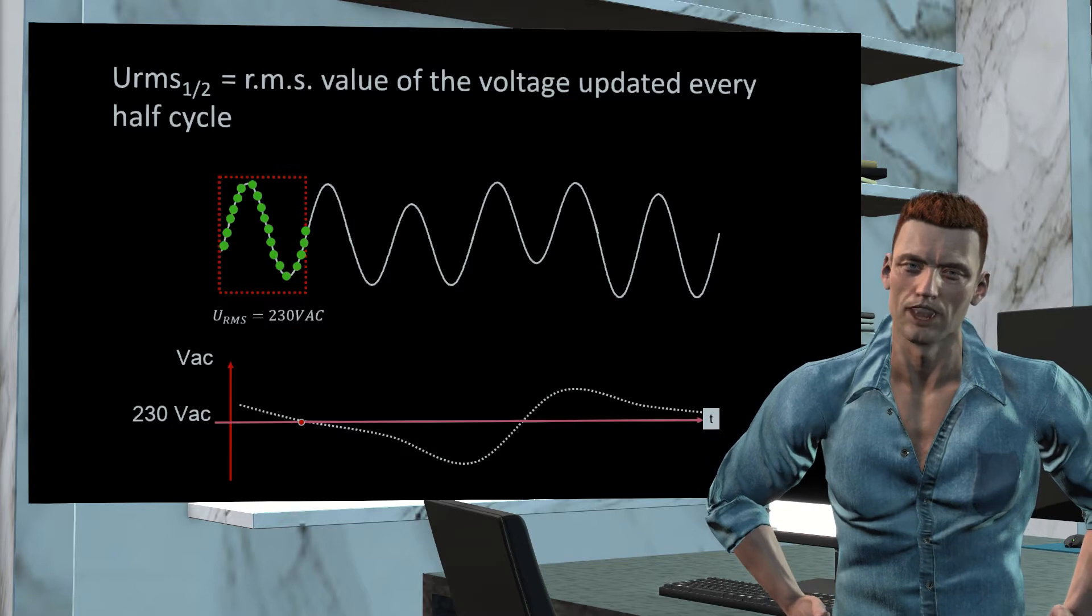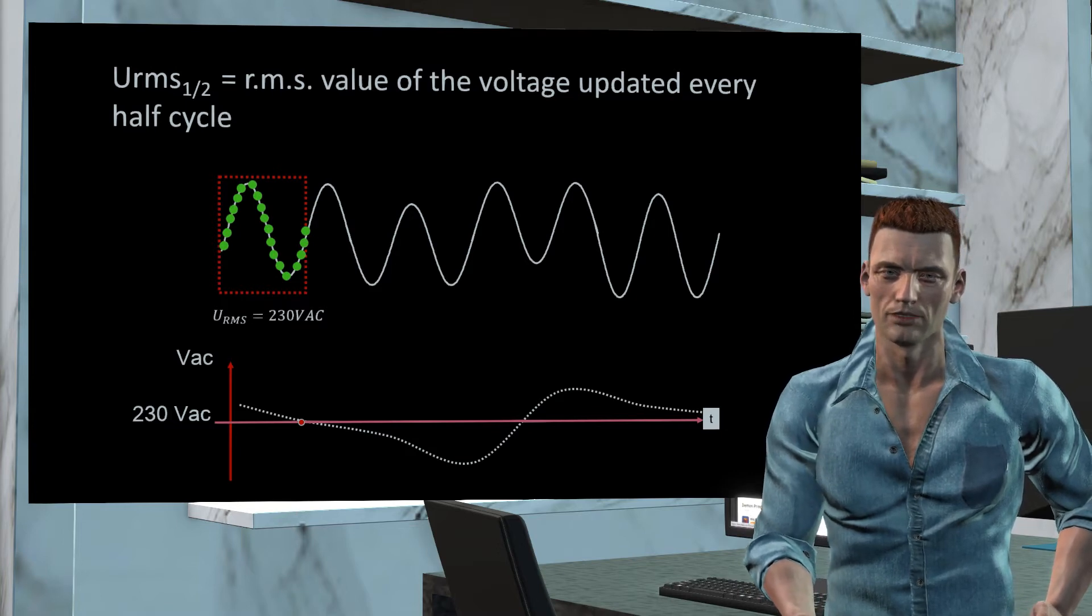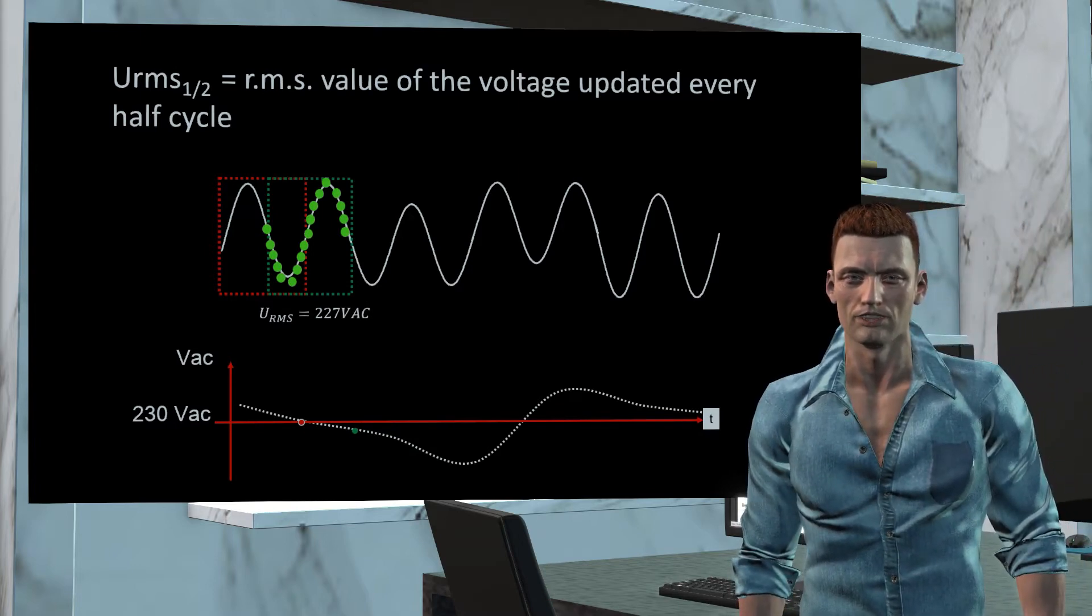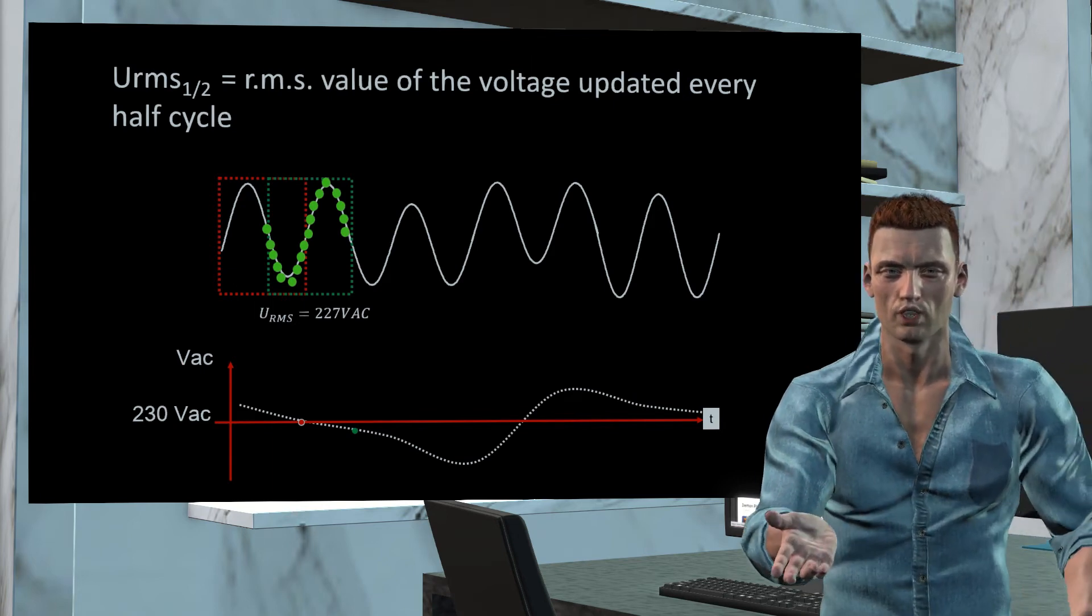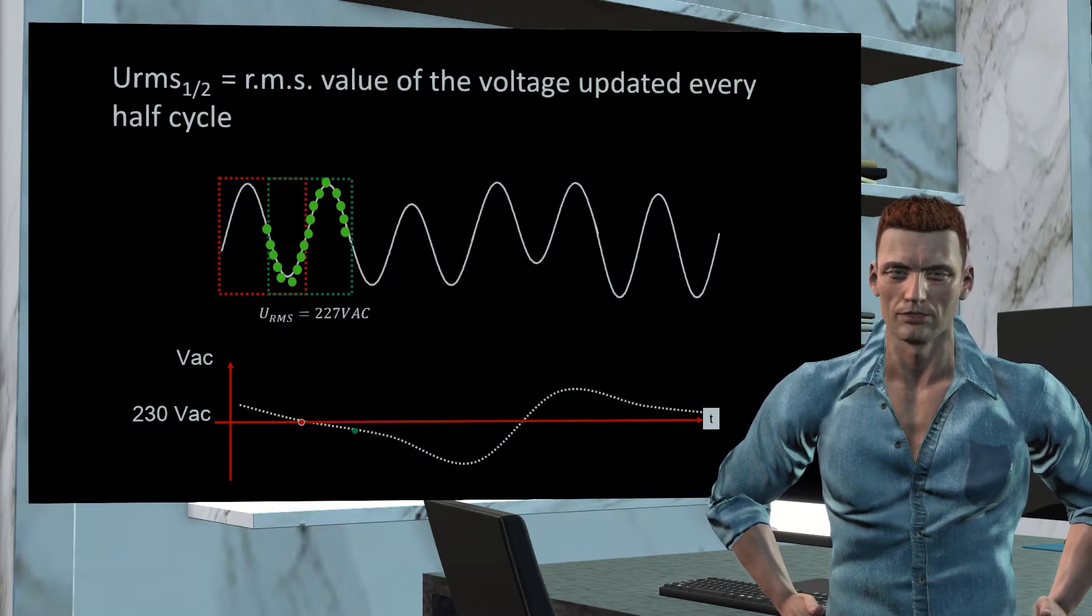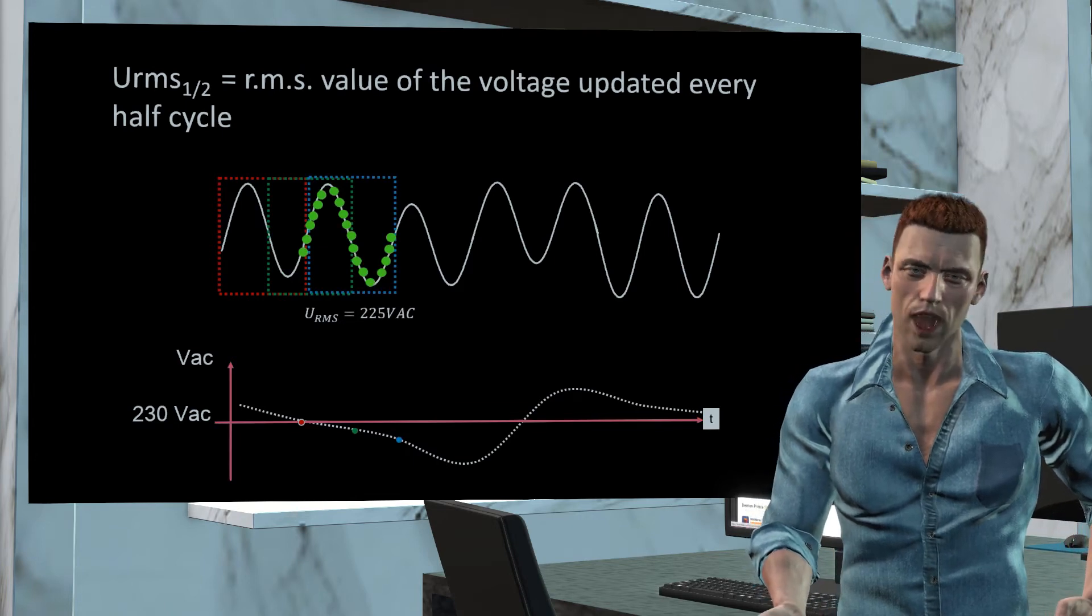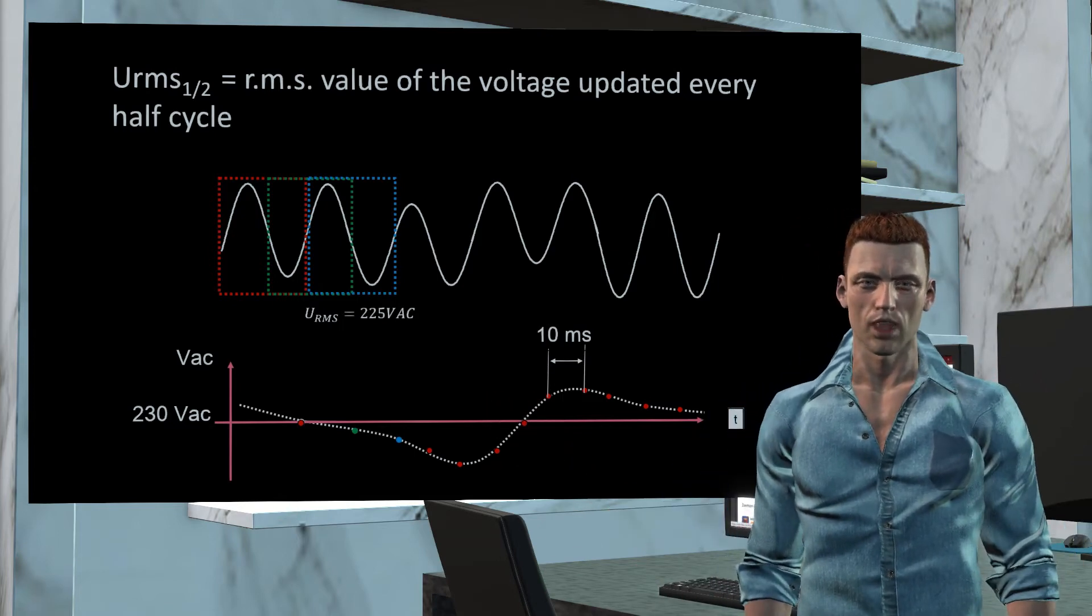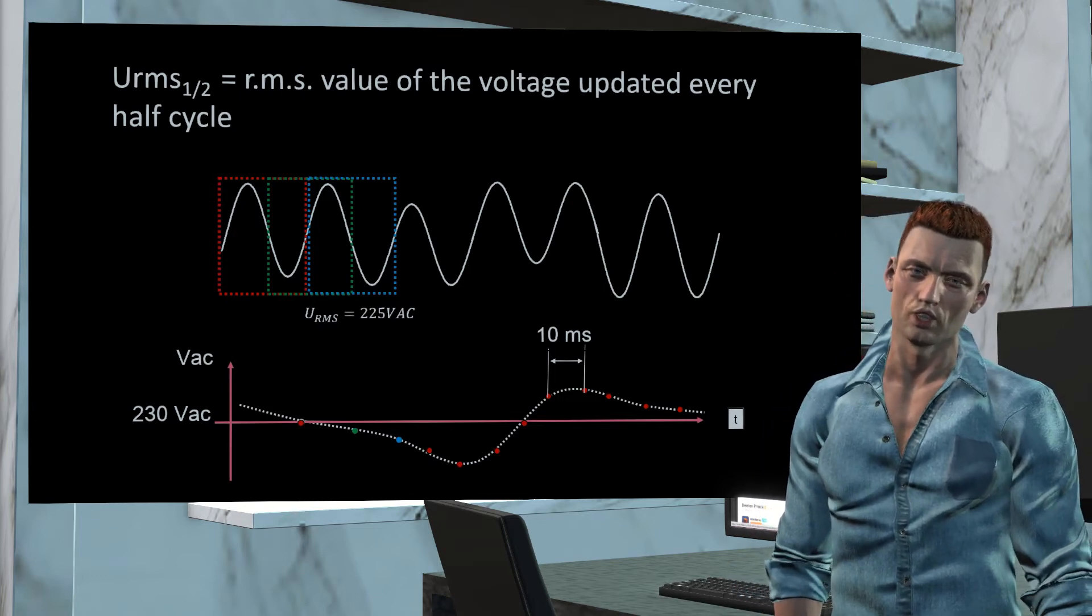Since the analyzers must record the data, this process of sampling and calculating the RMS value must be repeated continuously. To avoid the possibility of a small missing period of time between two consecutive RMS values, what the analyzer does is start the second calculation before the previous calculation has finished. In this way the measures of effective values are obtained every 10 ms, even if each value is sampled for a full cycle. In this way, dead times between two consecutive effective values are avoided. Here we can see the calculation of a third RMS value. In short, RMS measurements are obtained every 10 ms, even though each value is sampled for 20 ms. This is the concept of URMS half-cycle voltage, that appears in much documentation.